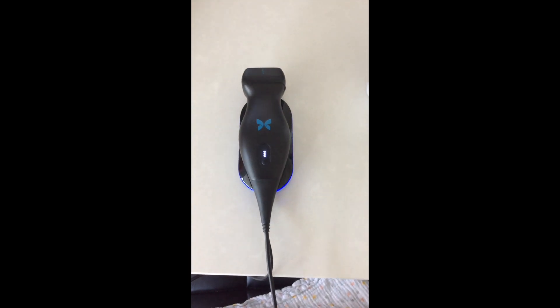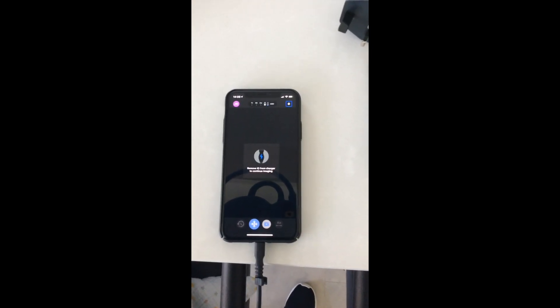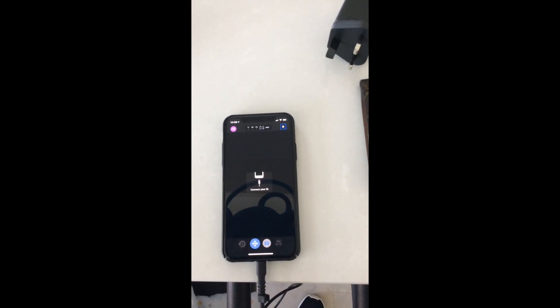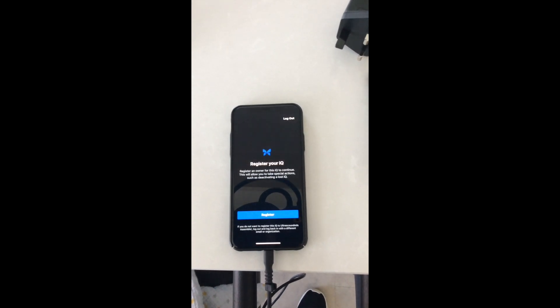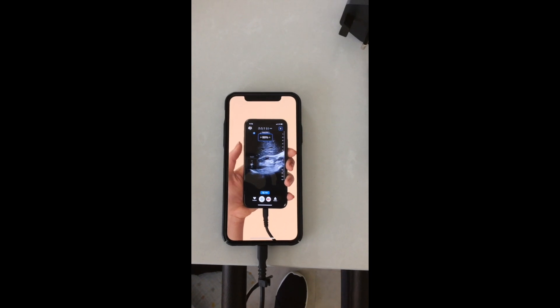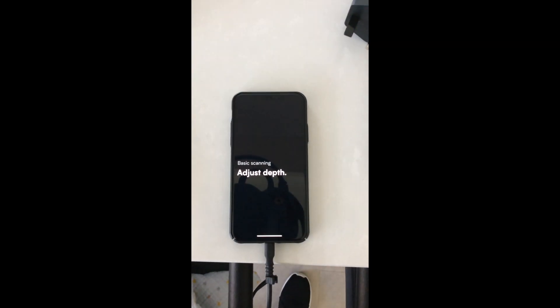With the software up to date, I'm actually using my son's iPad in a very garish case to film this. Probe's still on the mount. And we're ready. It's saying connect your IQ again — remove IQ from charger and continue imaging. Taking it off the charger now. It's connecting. I'm now going to register it. There's a very nice video going on here, step-by-step on how to use the app and the functionality of the probe. Swipe up or down to adjust the depth of your image, release your finger and the system will respond. Very tasty.